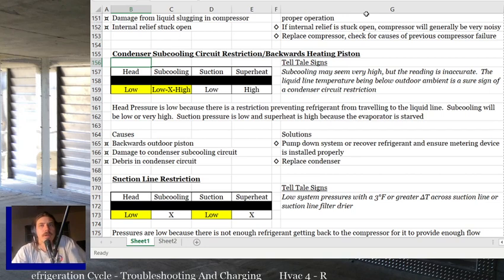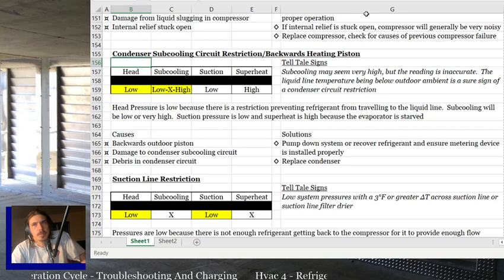You're looking for the low head pressure. You're looking for generally awful cooling performance, right? Because you're restricted. You basically have a liquid line restriction before you even hit the liquid line, so you're going to get crappy cooling performance. You're going to have low head pressure, and usually a liquid line temperature that is below ambient. Head pressure is low because there's a restriction preventing refrigerant from traveling to the liquid line. Subcooling will be low or very high. Suction pressure is low and superheat is high because the evaporator is starved.